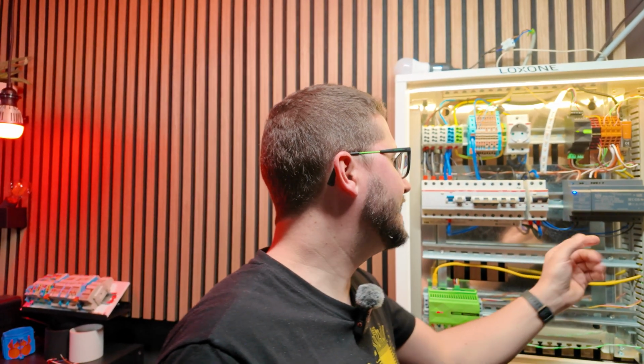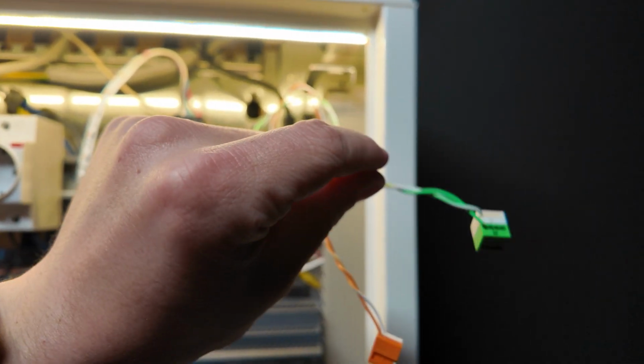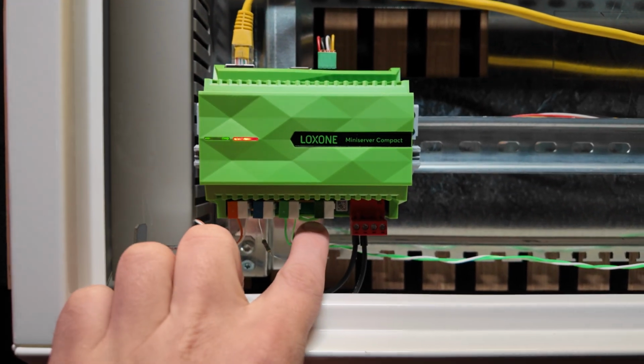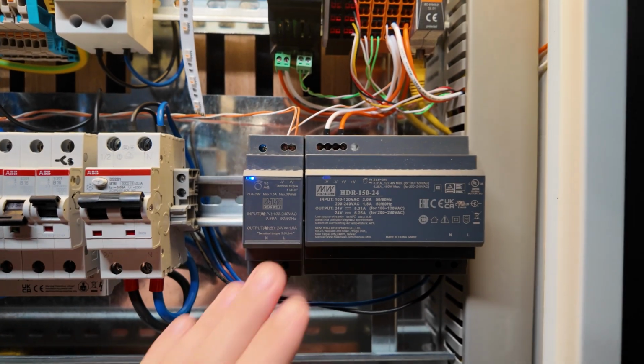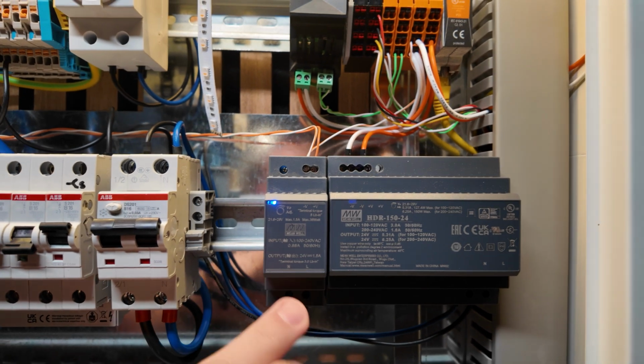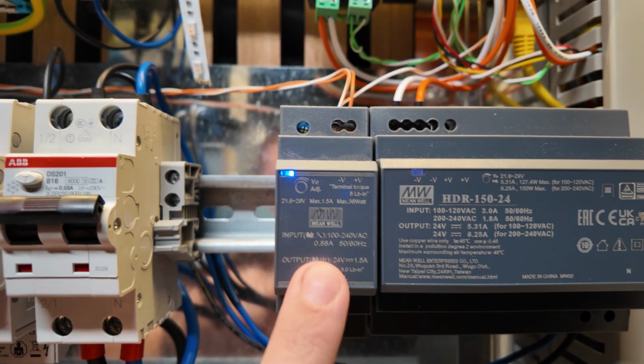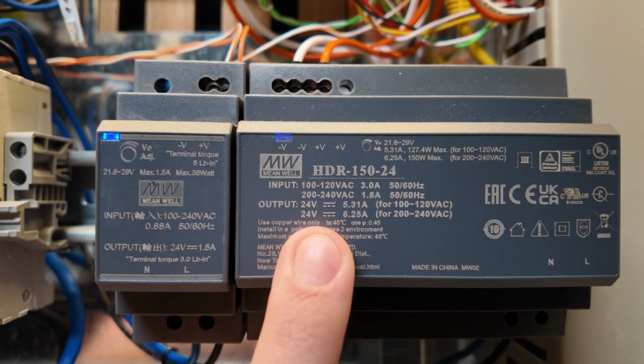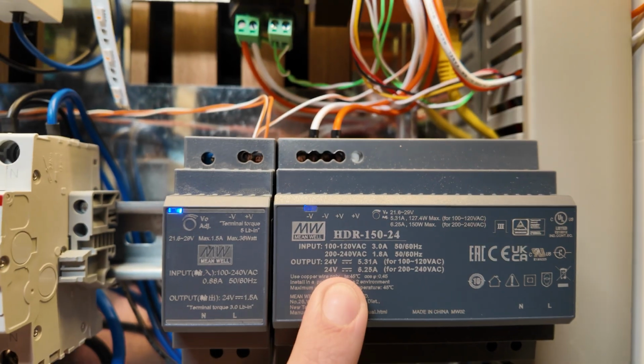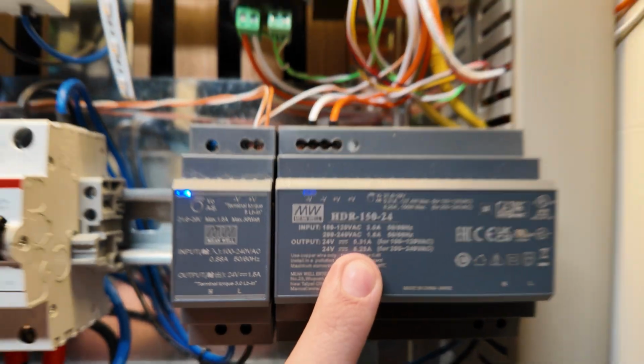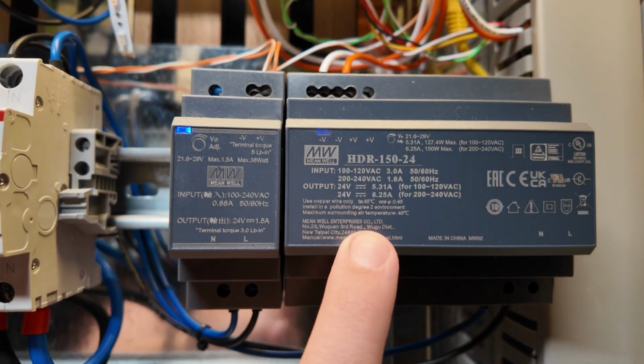This often is the result of the same topic, that this one power supply here does not have the same 0 volt reference as the other power supplies. I'm not 100% sure, but I believe the Tree and the Link bus, so from the Miniserver to its extensions, I think it's 5 volt, I'm not 100% sure. So if there is a slight difference between the 0 volt from this one to the 0 volt of that one, for whatever reason, this might lead to bad communication, and especially if there is a lot of things happening.